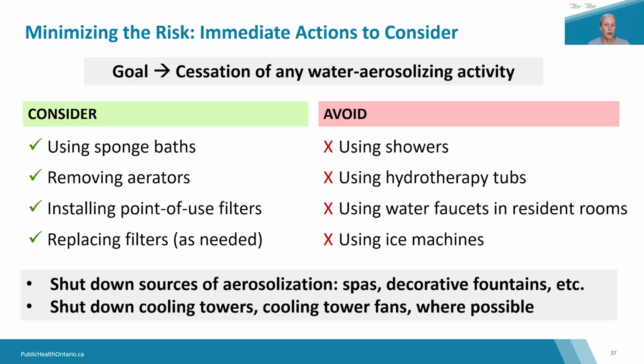You may consider installing water filters capable of filtering Legionella and replace them according to manufacturer's instructions. Where possible, you may shut down any unnecessary sources of aerosolization like fountains or hot tubs. And for cooling towers, while it's not always possible to shut them down, especially in the middle of summer, water system consultants can support facilities with these challenges, and you may be able to remediate a cooling tower without having to shut it down. But every system is different and requires an individualized approach. Next slide, please.